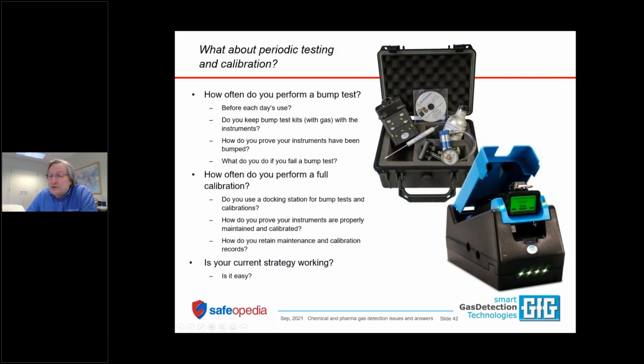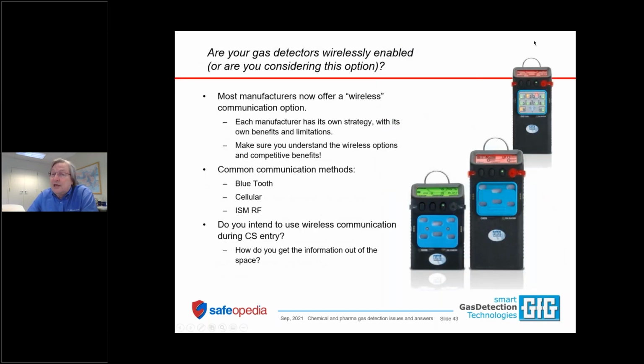Again, when it comes to bump tests, make sure that if you are committed to performing a bump test before each day's use, you have the materials living conveniently in the same place where the instruments live. Make sure if you're using a docking station that the docking stations are located conveniently where people can actually use them to perform the tests.